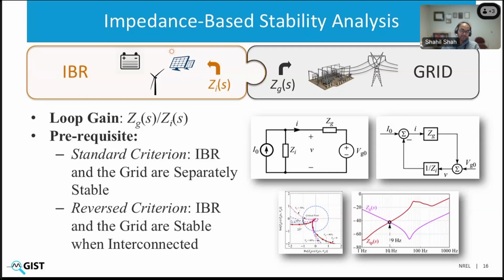You can have the same set of impedance responses that you have scanned before for the grid. And it can be from different points of interconnection. It can be for different dispatch conditions. And once these impedance responses are obtained, they can be stored in some repository, and you can mix and match any IBR impedance, any puzzle piece that represents IBR, and match it with the grid and see if they will create an instability or not. When you connect the two impedances, they form a negative feedback loop.